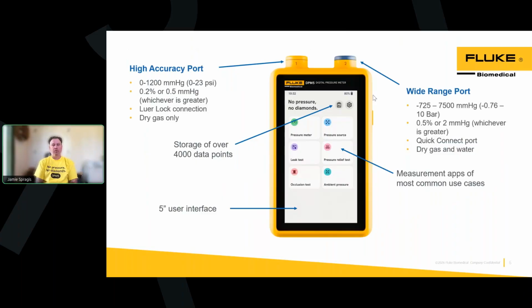Now let's talk about the 2 ports. Here you can see on the left is our high accuracy port, used for non-corrosive gases, and it's also the side that your pressure pump generates your pressure. So the apps that generate pressure are going to be on port 1. And here you can see the high accuracy port is from 0 to 1200 millimeters of mercury, or 23 psi. Super accurate specs with 0.2% or 0.5 millimeters of mercury, whichever is greater. And then port 1 has a luer lock connection. Really, really important. Port 1 having a luer lock, port 2 having a quick connect.